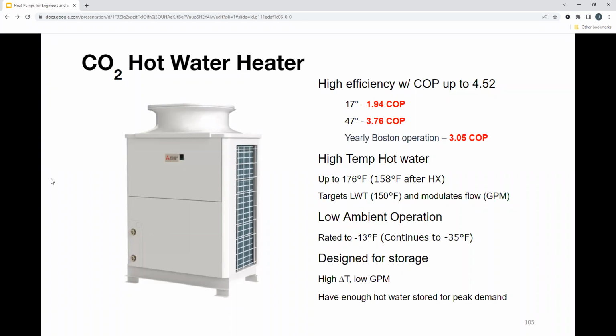And the whole mindset needs to be changed a little bit when we're talking about domestic hot water. Typically, you're going to have a large source with little to no storage. It's more of a demand response. That is not the case here. This is designed for a small source and larger storage, right? So we're looking for a high delta T with a low GPM associated with that. And then we are storing enough water for that peak demand, whatever that is, how many GPMs it needs, at that time.